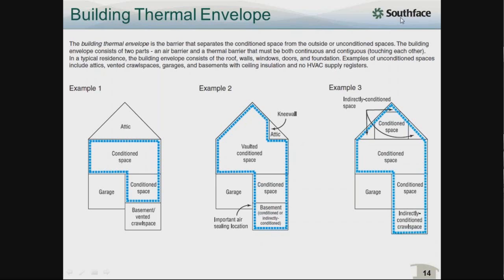And of course, some materials can function both as an insulation and an air seal at the same time, and that's just fine too. For things like spray foam, it'll be both. It'll always be in the same plane. But if you're using air permeable insulations like fiberglass or cellulose, they have to be in conjunction with an air barrier. It actually has to be in contact with it.